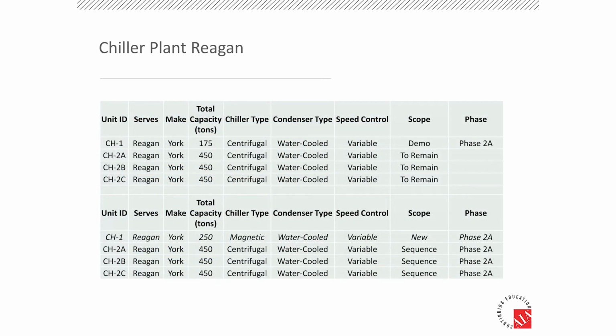Yeah. So in the load analysis, this is the original plant. They were all York machines. It was a York plant. They're all variable speed. We only changed out the one machine because there really wasn't enough runtime on the other ones. Absolutely not enough runtime on this one. And we upsized it to 250 tons. Made it magnetic. It's a York YMC squared.